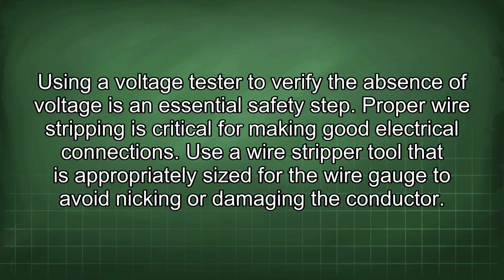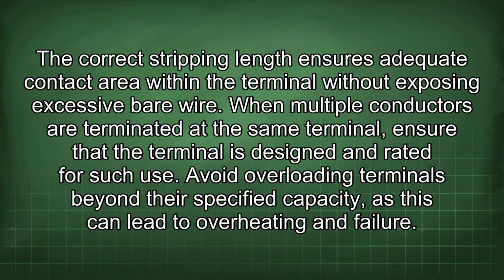Proper wire stripping is critical for making good electrical connections. Use a wire stripper tool that is appropriately sized for the wire gauge to avoid nicking or damaging the conductor. The correct stripping length ensures adequate contact area within the terminal without exposing excessive bare wire.